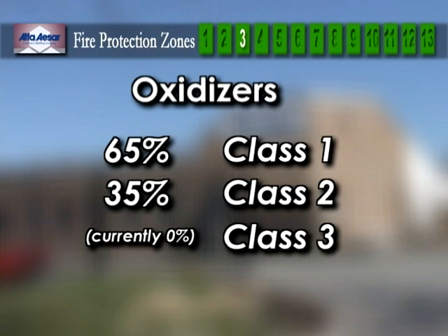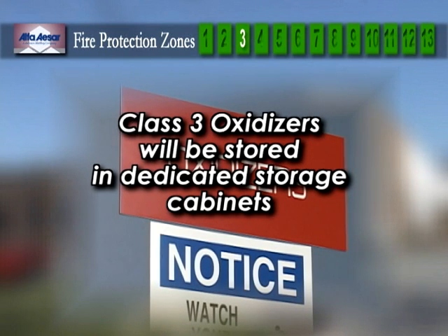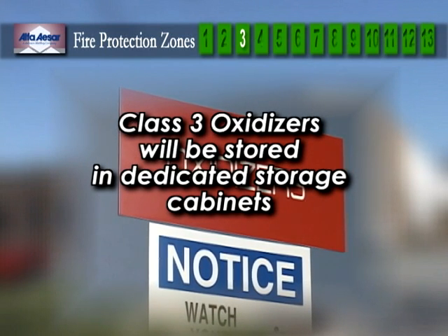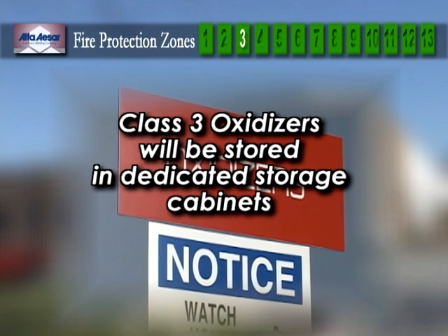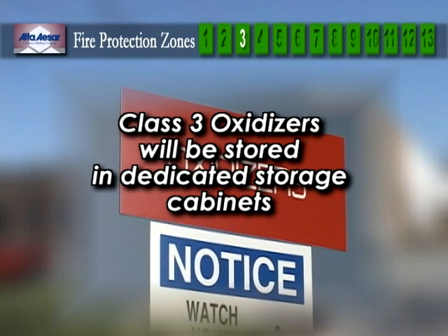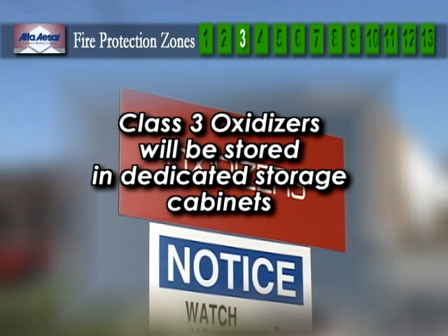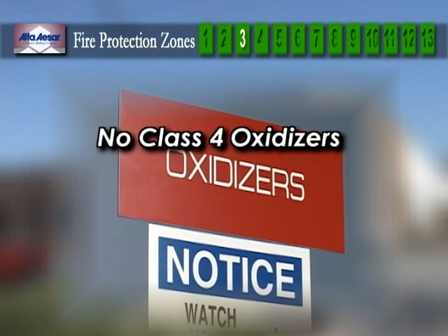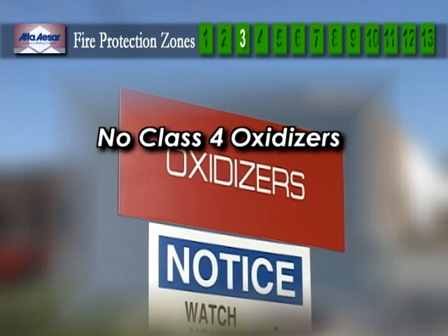However, should Class 3 oxidizers be placed into inventory, dedicated storage cabinets, specially constructed to house this material, will be provided. These containers are designed to be connected directly to the sprinkler system so that the higher sprinkler flow densities required for Class 3 oxidizers is limited to the storage containers rather than applied to the entire space. No Class 4 oxidizers will be held in inventory at this location.